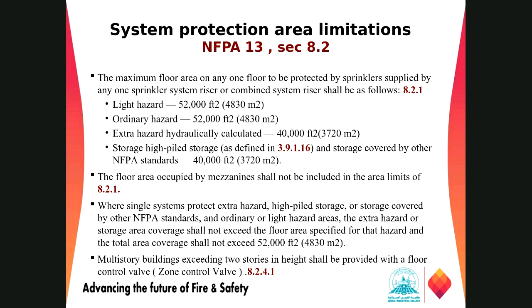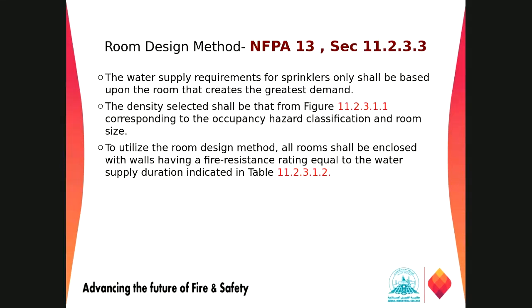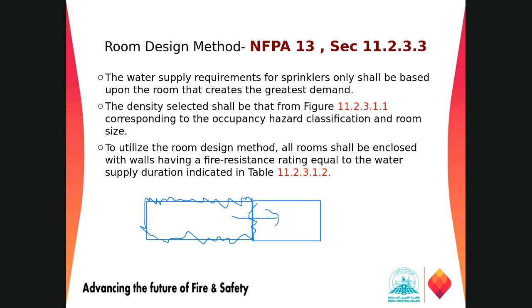How it works: suppose we have a room. Let's go to the previous slide. Suppose this is one room, and this is another room, right? So the duration of the water supply, suppose it is 1 hour. The fire rating should also be 1 hour between the wall, the opening and all, so that the heat cannot travel from one area to another area within 1 hour.